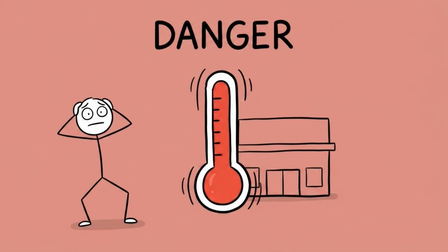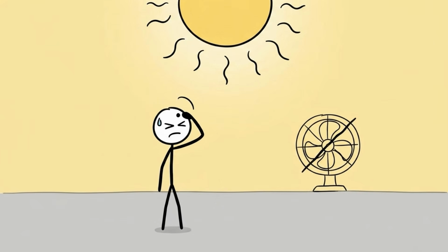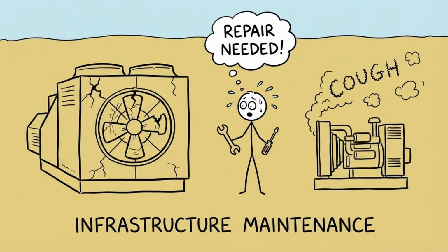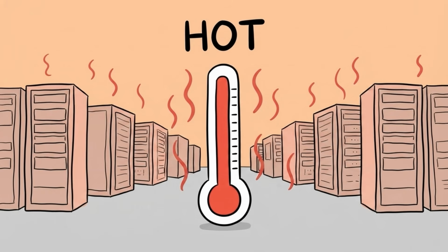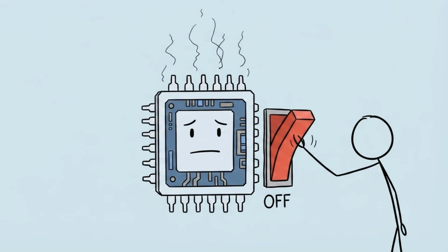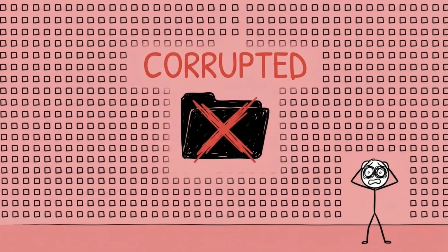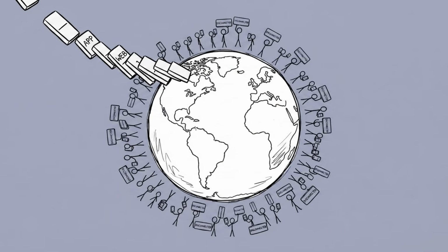Force 2: thermodynamics can kill the facility, and when it does, it's catastrophic. On a hot summer afternoon, if a chiller plant fails and backup generators stumble during a grid brownout, the internal temperature of a high-density server hall can rise to critical levels in minutes. When silicon overheats, servers automatically shut down to prevent damage, but a sudden mass shutdown across 50,000 servers can cause data corruption, drop millions of active user sessions, and trigger cascading software failures globally.